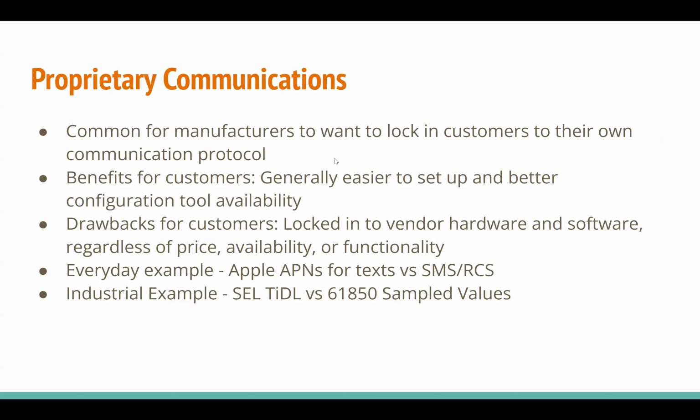So there are obviously some drawbacks that you can probably immediately see from that. If you use proprietary communication protocols, you can only ever buy the device from that certain manufacturer that made it, unless they license it to somebody else. But there can also be another drawback: if that vendor ever stops supporting that communication protocol, like they're just like, oh, we don't like TiDL anymore, we want to move forward with something else, we're not even going to make any new devices that have that, then you have to basically replace everything that you have because you can't talk in that communication protocol anymore. There's nothing else that exists to talk in it.